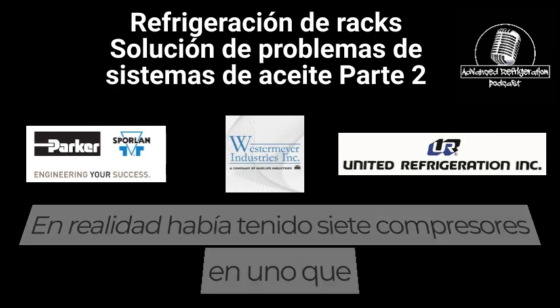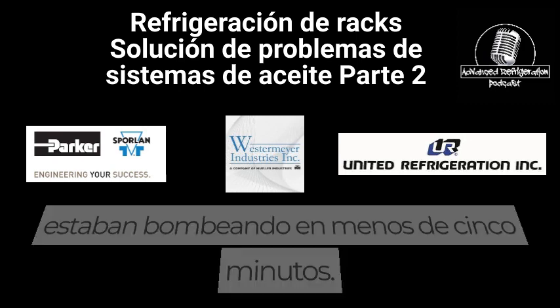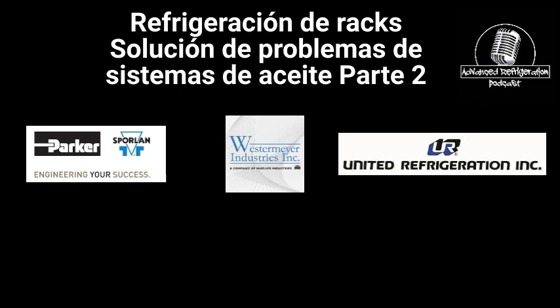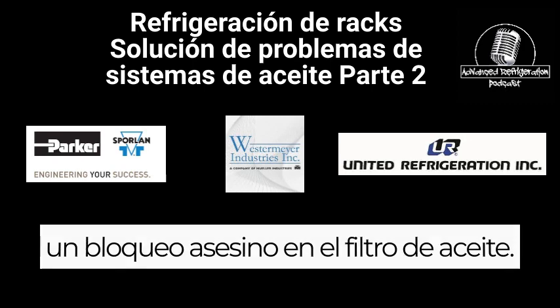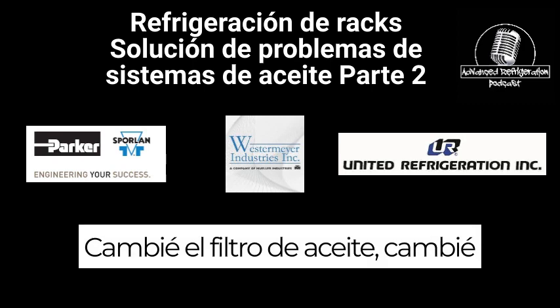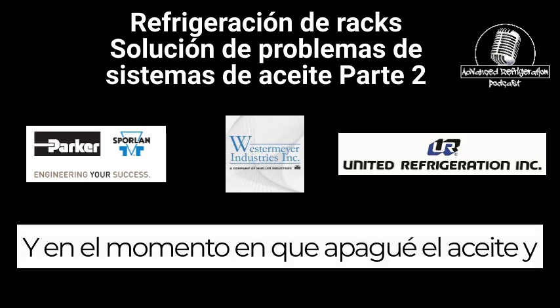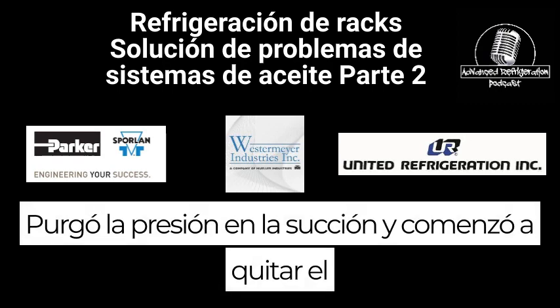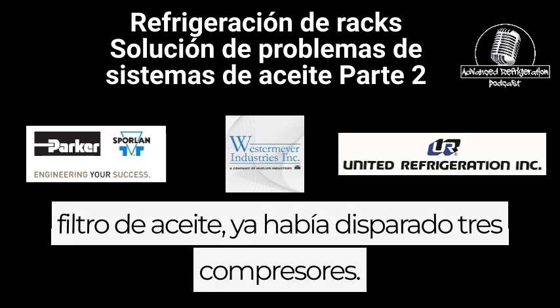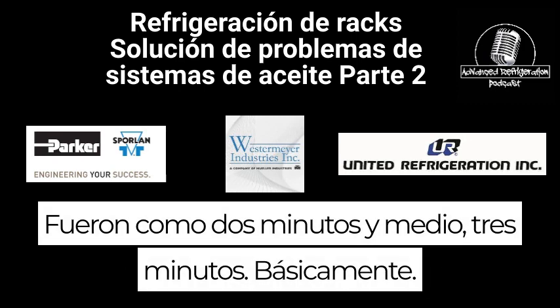Yeah, maybe. I actually had seven compressors on one rack that were pumping out in less than 5 minutes. I thought maybe I just had a killer blockage on the oil filter, so I changed that because the oil looked dirty. I changed out the oil filter and the Y1236, the oil regulating valve. By the time I shut down the oil, bled off the pressure in the suction and started removing the oil filter, I had already had three compressors trip on oil fail. They had pumped out. I timed it. It was like 2.5 to 3 minutes.